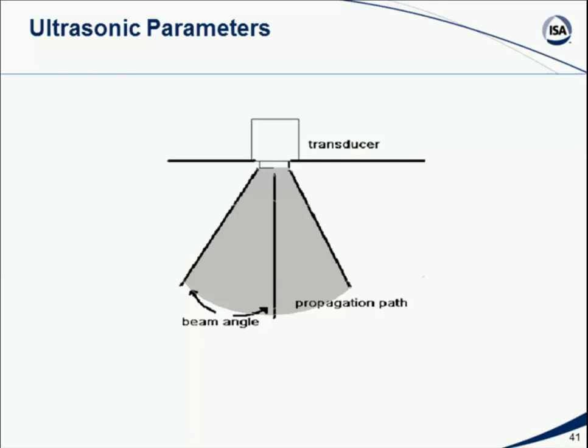For example, depending on what's in the tank, if you have a lot of suspended particulates and dust in the tank, that can actually cause false readings. Or if the tank has a lot of appurtenances sticking into the tank on the sides, and you haven't aimed and focused the ultrasonic transceiver appropriately, you might actually hear a reflection off of one of these appurtenances or obstructions and think that that's the level versus the actual level. But if you follow the manufacturer's instructions and set things up appropriately, ultrasonic measurement can be used quite successfully in a lot of applications.